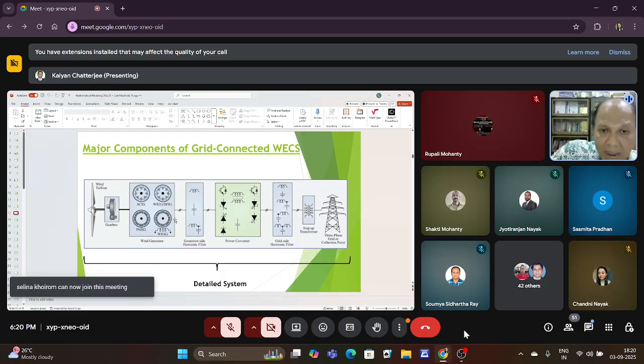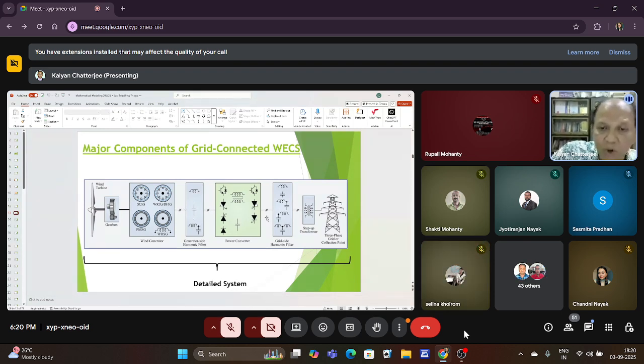After that, a harmonic filter is required before the converter circuit. We use generator side filtering, and there are two filters: one is the generator side, and after the power converter, the grid side harmonic filter. Two filters are required. Then the step-up transformer. So again, there are three parts.